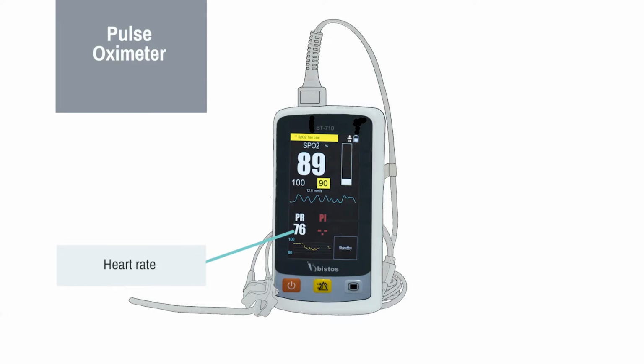The largest number in the top left-hand corner is the saturation level. As long as you are in the correct setting, an alarm will go off if the saturation is below the target level. The middle button at the bottom resets the alarm. The targets for the saturation levels are immediately below the SpO2 reading. In this case, the target is between 90 and 100%.